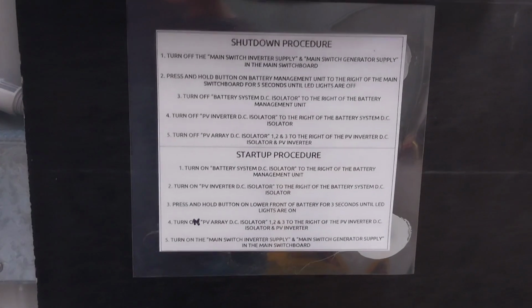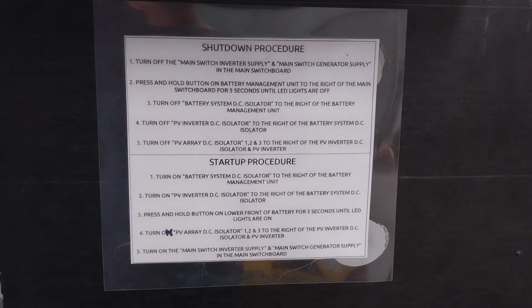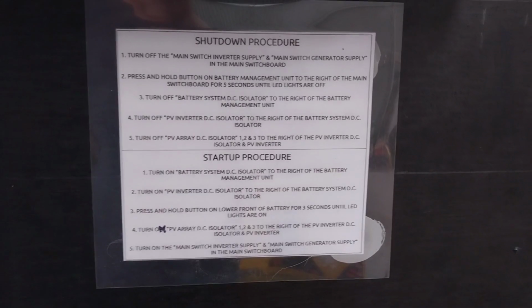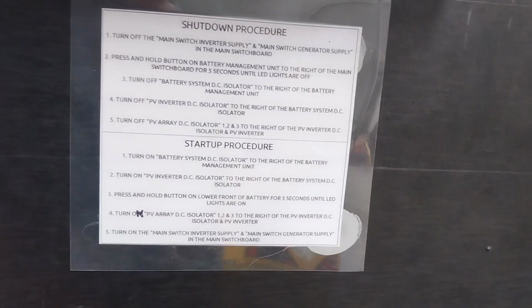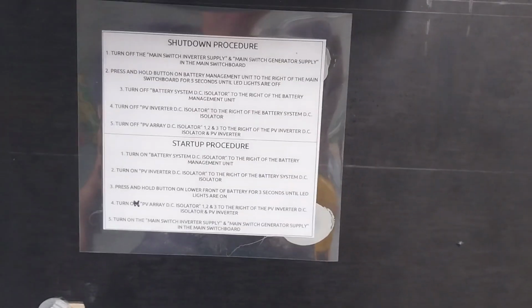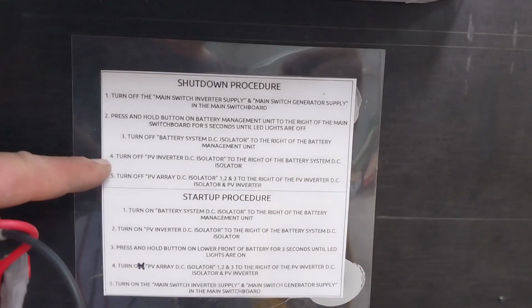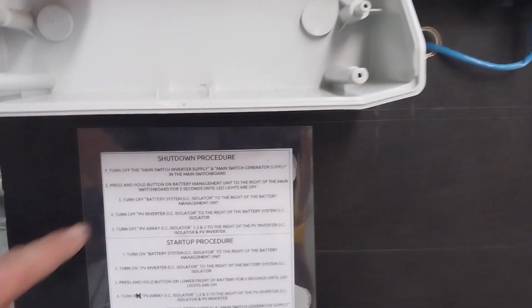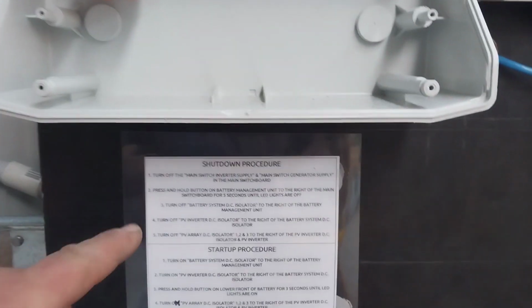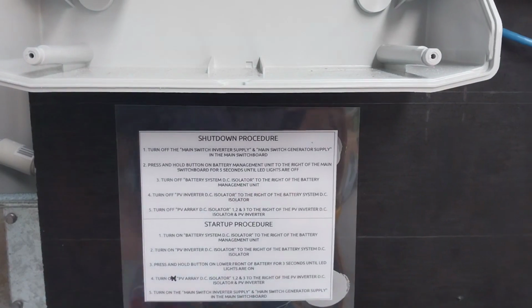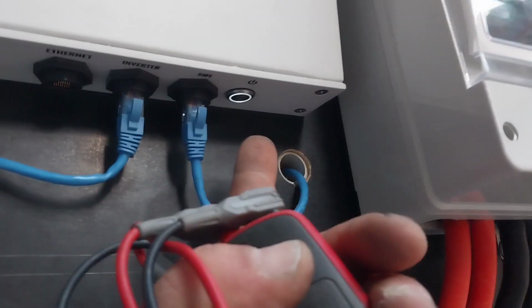I've got my shutdown procedure there and my startup procedure. You can freeze that if you want to copy it. Yes, I know I left that as off when I cut and paste. I just changed the order for startup from shutdown. Obviously, shutdown is all about keeping the load off when you switch any DC breakers. So we start with the AC off first, and then we turn off the battery with this button here. We hold that for 5 seconds, and then we can turn off all the DC isolators.